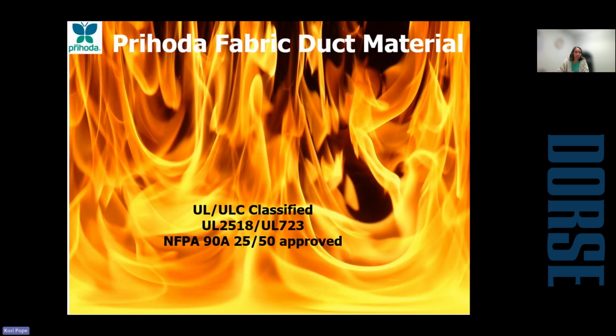So all of our ductwork is made from highly engineered polyester, and we chose that material because it's not going to rust, corrode, and it's not going to retain any type of moisture. Polyester itself is also inherently antimicrobial because it's not going to promote any type of organic growth. So all of our commercial fabrics are UL and ULC listed, and they are approved under the NFPA 90A, so they're going to meet all of the building codes.